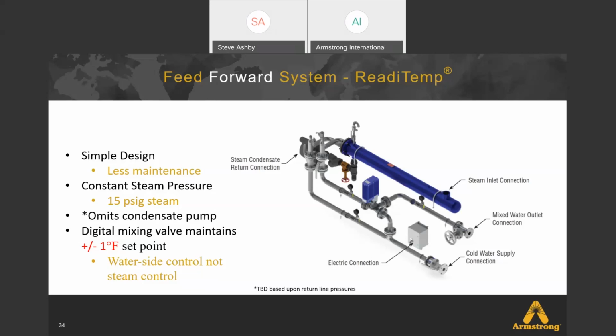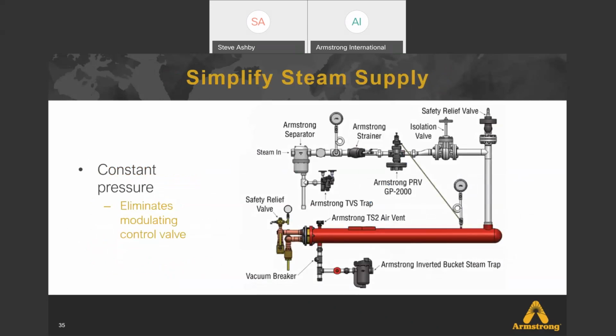And then we have overheated water, again, that comes to our mixing valve. And then we blend with cold water. We're able to deliver an immediate temperature on demand. With the constant steam pressure now feeding the heat exchanger, this simplifies the steam supply part of the installation. We have to reduce the steam pressure down from plant pressure greater than 15. We'll take 100-pound steam, reduce it to 15-pound, feeding the shell, and that's it. There's no modulating control valve required.